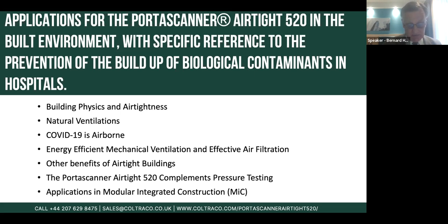Other benefits of airtight buildings. As mentioned, other benefits of airtight buildings include thermal comfort, acoustic insulation, pest and infestation control, prevention of water ingress, and fire suppression. Maintaining oxygen levels, either to prevent a hypoxic environment for health and well-being, or to create a hypoxic environment to reduce oxidization and to suppress or prevent fire, require these spaces to be kept airtight. With a Portascanner AIRTIGHT 520, buildings fitted with fire suppression systems can now undergo frequent and regular air tightness checks to ensure that the fire suppression systems are effective by preventing the infiltration of oxygen through gaps or cracks in the building.